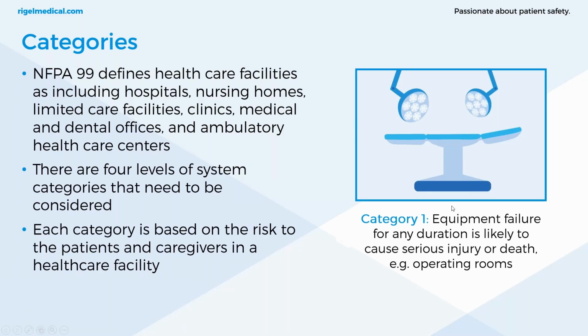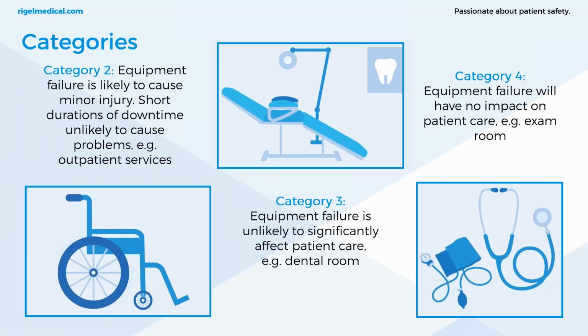So in the first slide, we've got category 1. This is where equipment failure for any duration is likely to cause serious injury or death, e.g. operating rooms. And then we've got category 2, which is where equipment failure is likely to cause minor injury. Category 3, equipment failure is unlikely to significantly affect patient care. An example of that is a dental room. And these are given within the NFPA 99 code.